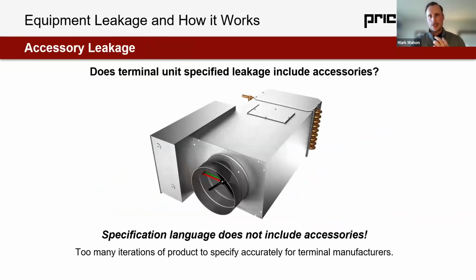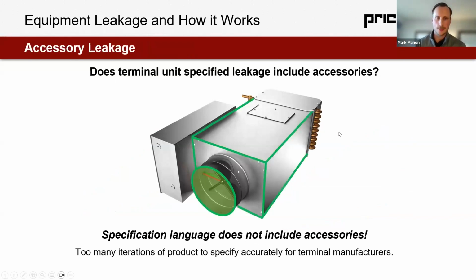So that's our equipment leakage. That's the casing leakage. But does terminal unit specified leakage include accessories? The answer is no. And it's unfortunate, but it's true. The main reason why is there's so many iterations of product, you know, different rows of coil, different sizes of coil, different access door options, whether it's screws or different latches, top and bottom access doors, different sizes of access doors. Price terminals have silencers, as do others. Electric coils are another option that leak very differently, and I'll speak to that.